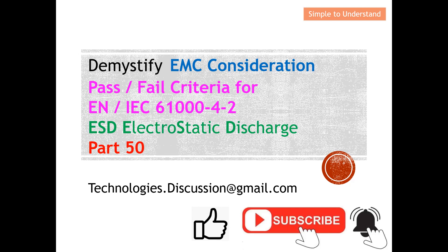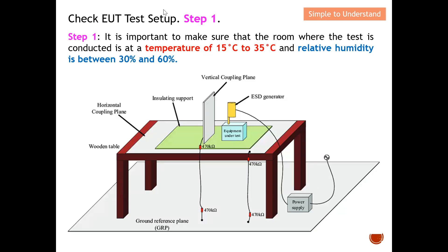Let's understand the 10 steps to check your EUT test setup for this standard. Step number one: it is always very important to ensure that the room where the test is conducted has a temperature between 15 to 35 degrees Celsius, and the humidity in the room must be between 30% to 60%.